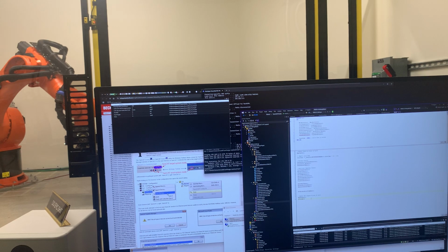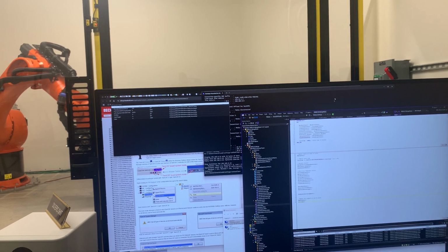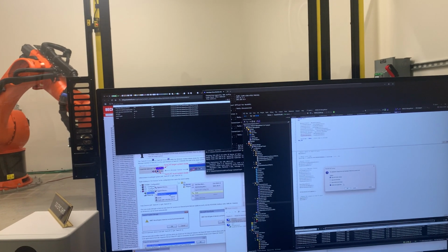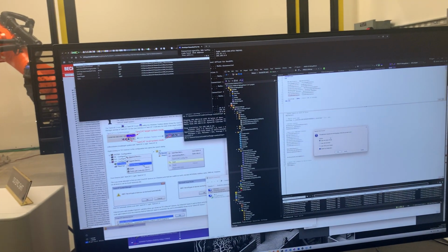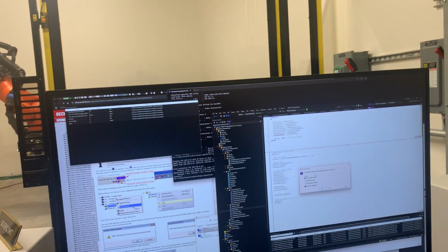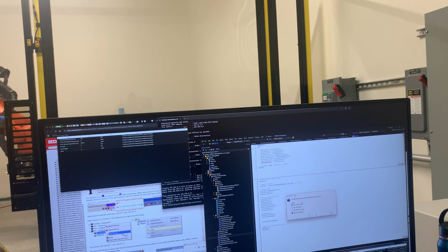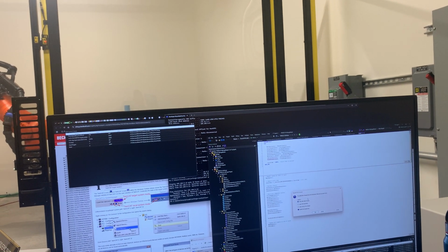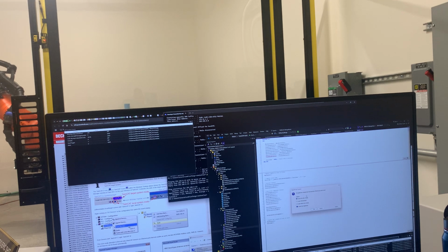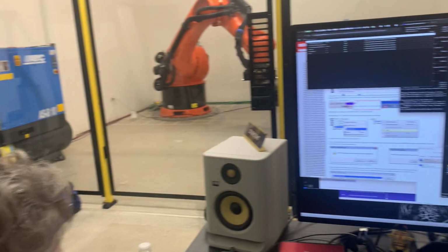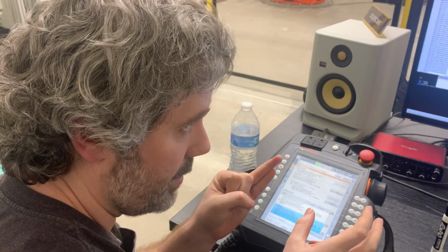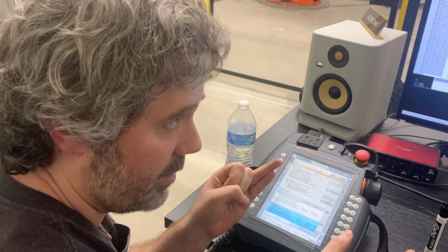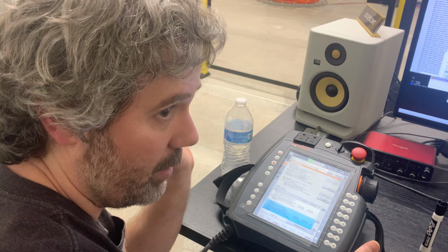If you log in now, it should say, okay, I've detected these are your options. Generally, you always want to update the boot application because that's updating whatever's going to start next time you power on, which you want your latest code to start. Log in with online change will attempt to look at the changes you've made and just load the logic changes without stopping the PLC from running.